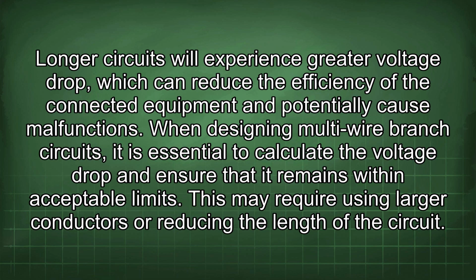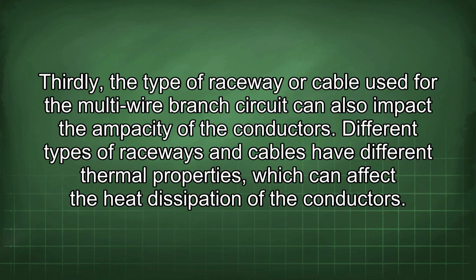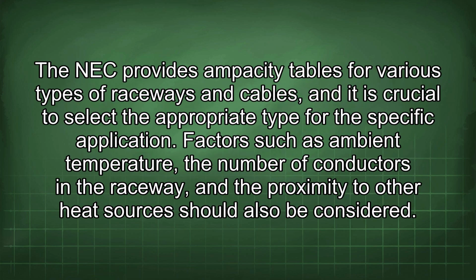This may require using larger conductors or reducing the length of the circuit. Thirdly, the type of raceway or cable used for the multi-wire branch circuit can also impact the ampacity of the conductors. Different types of raceways and cables have different thermal properties, which can affect the heat dissipation of the conductors. The NEC provides ampacity tables for various types of raceways and cables, and it is crucial to select the appropriate type for the specific application.